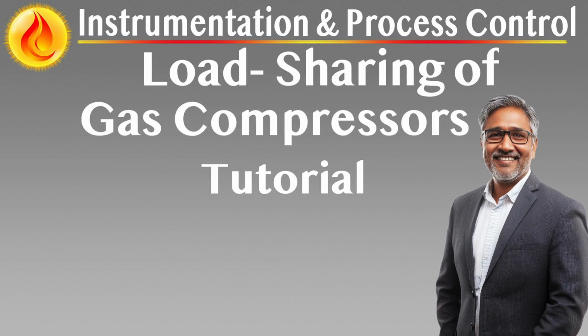Core functional roles. Station controller functionality continuously measures the selected capacity control variable, flow or pressure, calculates the deviation from set point and applies PID logic to generate a control signal. Issues a station control response, CRSC, to all associated controllers: load sharing controllers for normal throughput modulation, and anti-surge controllers for coordinated surge management during recycling.